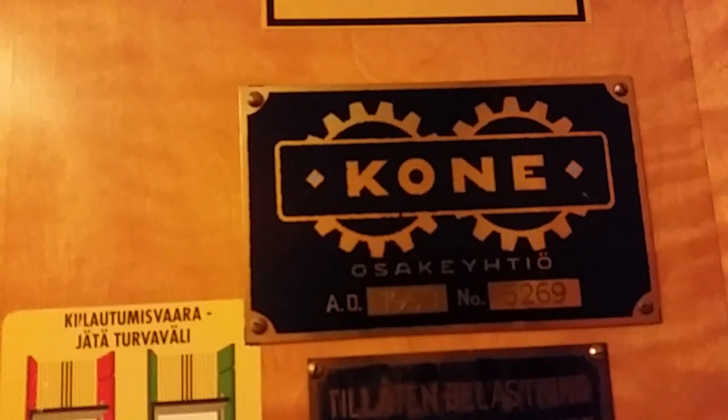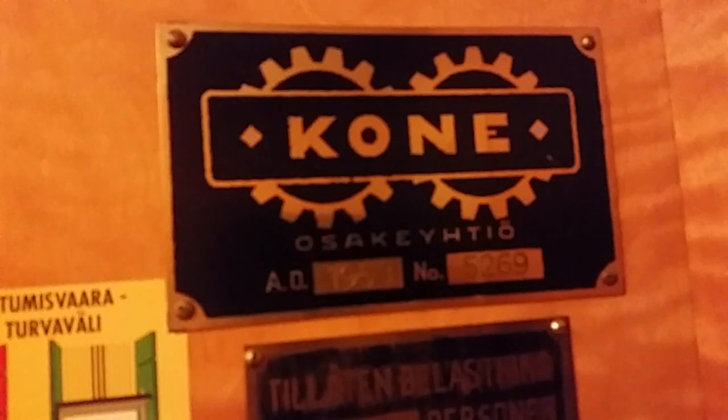There's a switch there. It can take four persons. Made in 1953, made by Connell — Kone. That will happen to you if you have goods in here: there is no soft stop on this one. It just brakes directly, then opens the door of course.